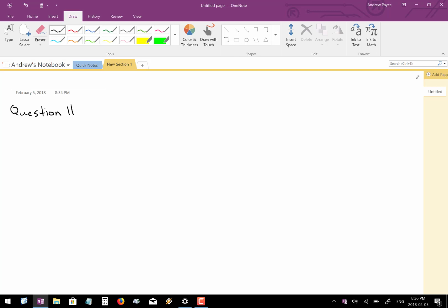Okay, so before we can start this question, we have to first figure out what our original motor was operating at. So I'll represent the values of the motor on a triangle, okay? My triangle is going to represent three things. It's going to represent the line current of the motor originally, which was 75 amps, and it's also going to represent my power factor, 0.7.